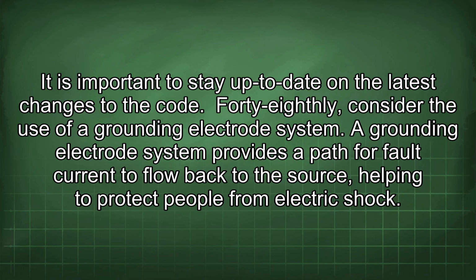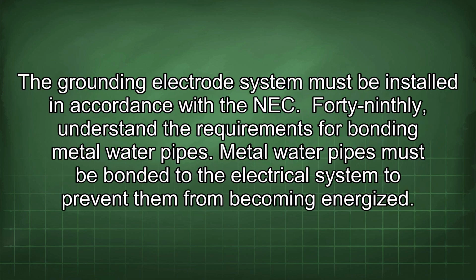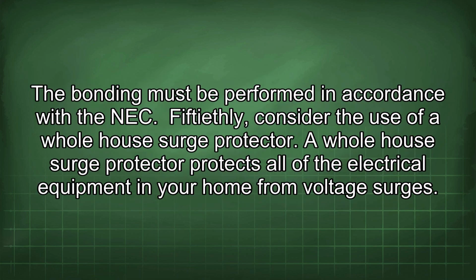48th, consider the use of a grounding electrode system. A grounding electrode system provides a path for fault current to flow back to the source, helping to protect people from electric shock. The grounding electrode system must be installed in accordance with the NEC. 49th, understand the requirements for bonding metal water pipes. Metal water pipes must be bonded to the electrical system to prevent them from becoming energized. The bonding must be performed in accordance with the NEC.